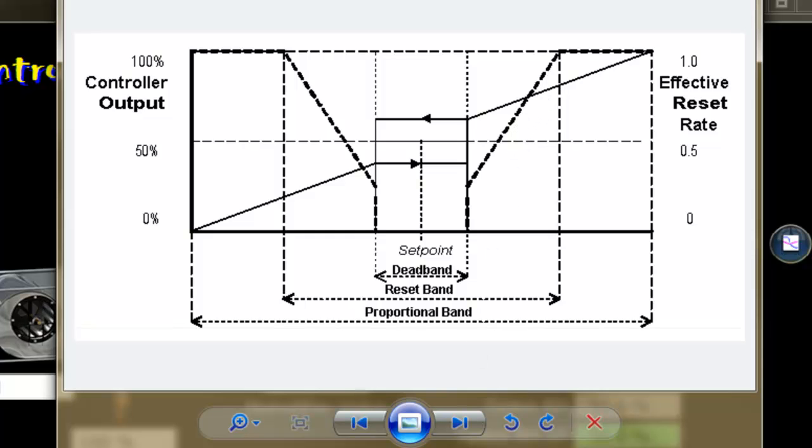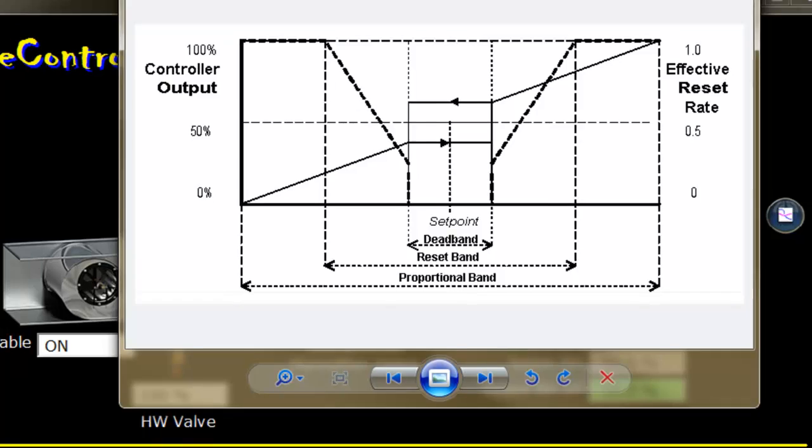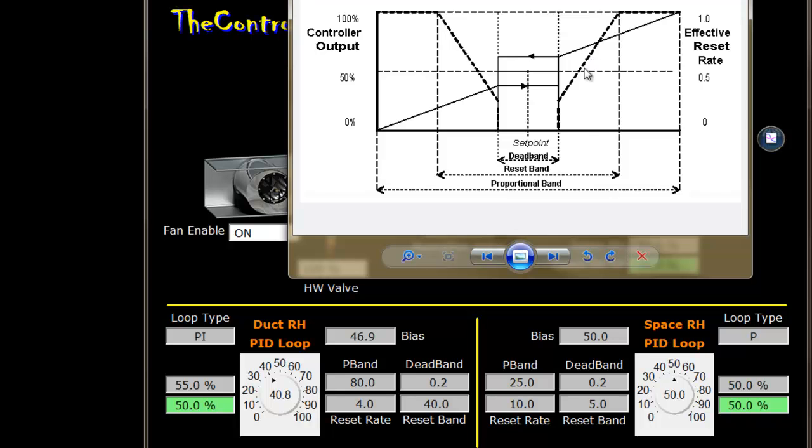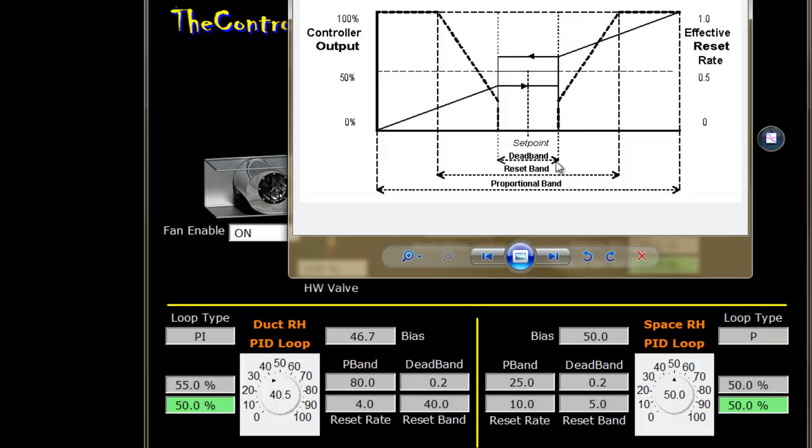The logic of the sliding scale is that if we get closer, we don't need to move that quickly. As we get closer to set point, the effect of the reset rate is diminished. If it was moving the bias at 4% in one minute, and I was right here in the middle, it would be more like 2% every minute. As you get closer to set point, it's 1% every minute until you hit the dead band.